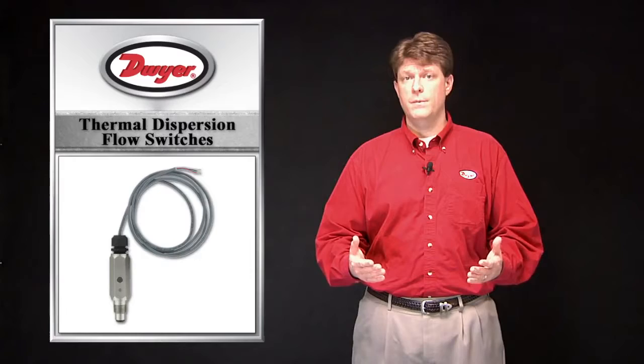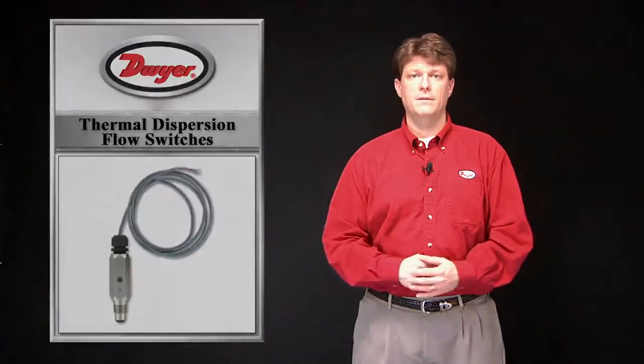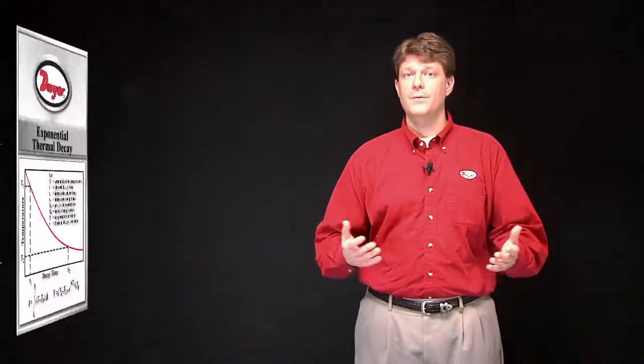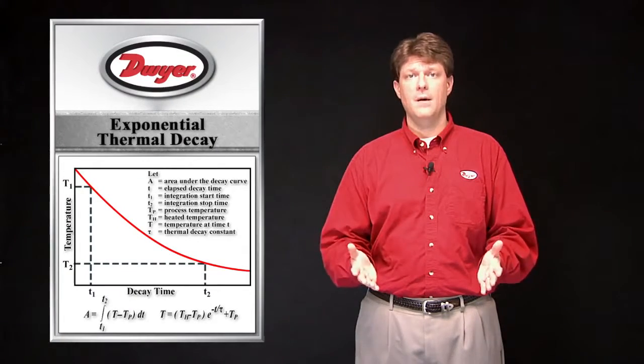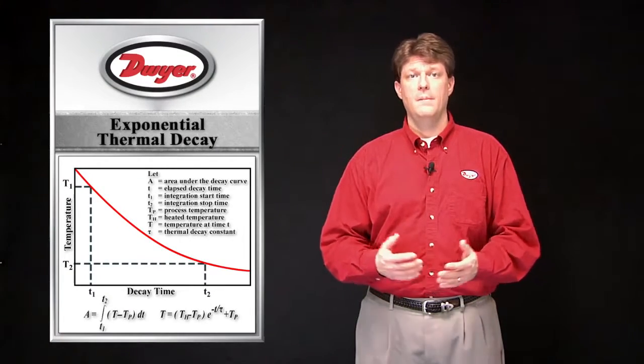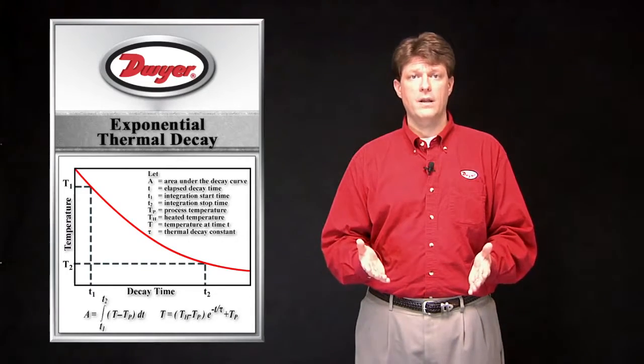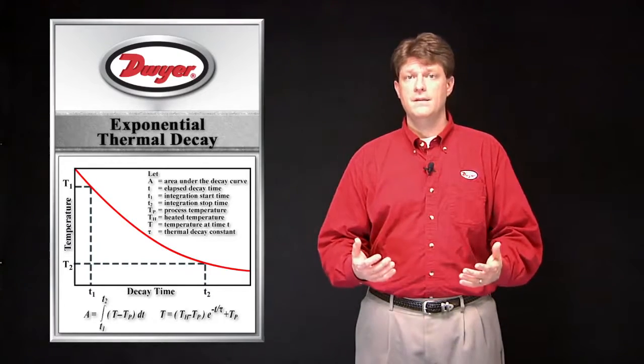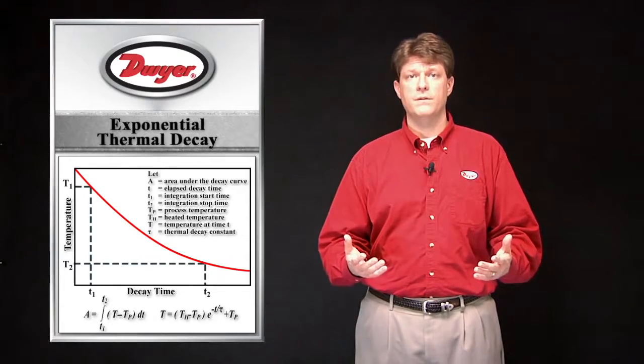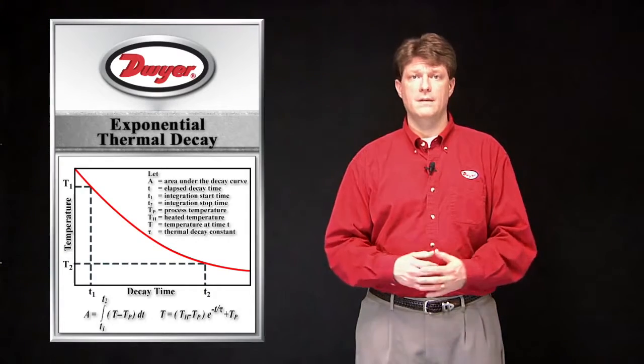Dwyer Instruments offers several flow measuring products that use a thermal sensing element. Thermal dispersion flow sensors use a temperature element that is heated up beyond the media temperature. Based on calorimetry, the flow moving past the sensor will have a cooling effect that is directly proportional to the flow velocity. The heat is convected from the heated probe surface to the boundary layer of the fluid flowing over the heated surface.